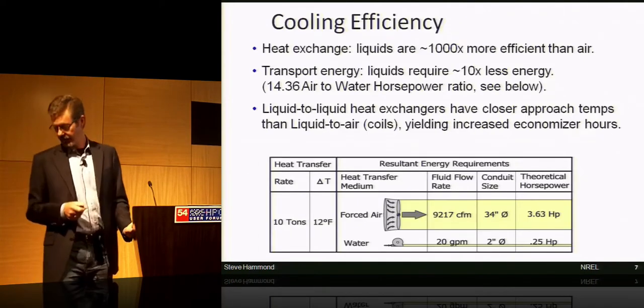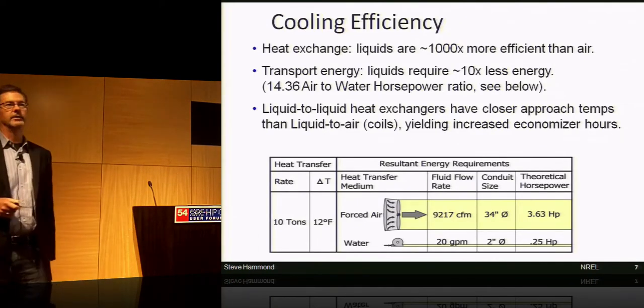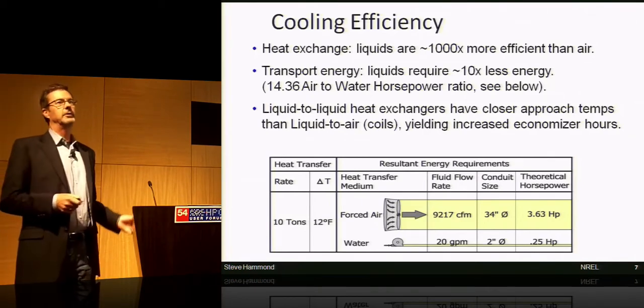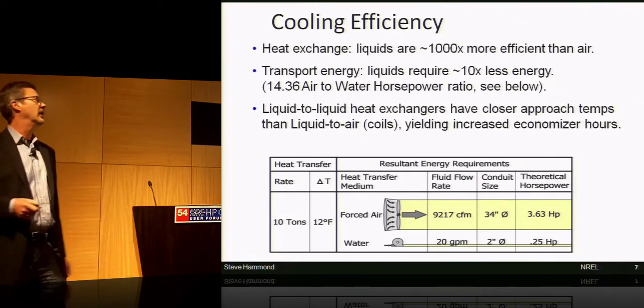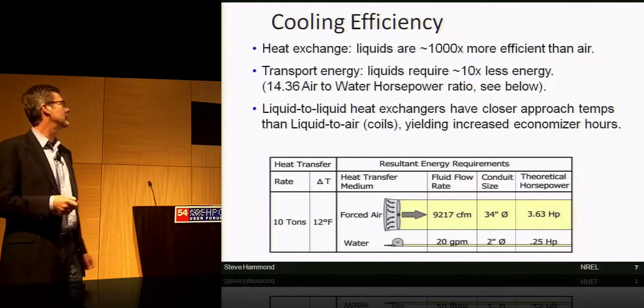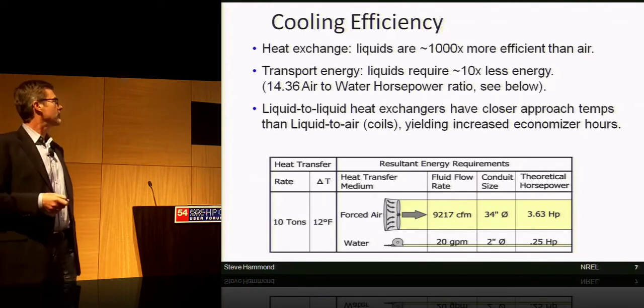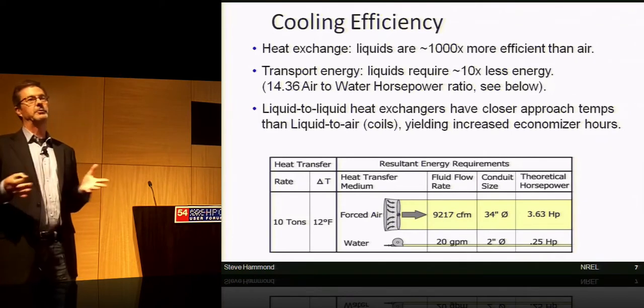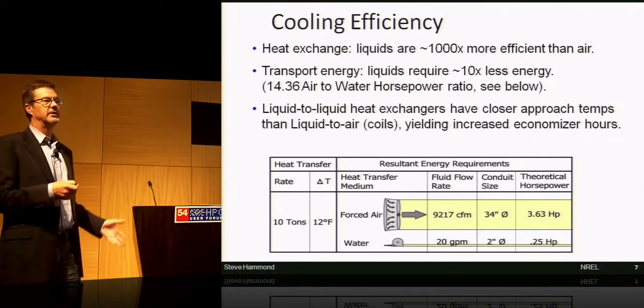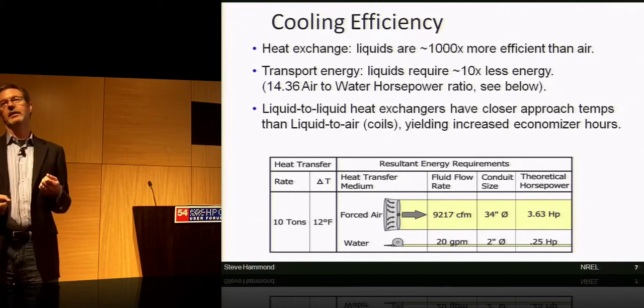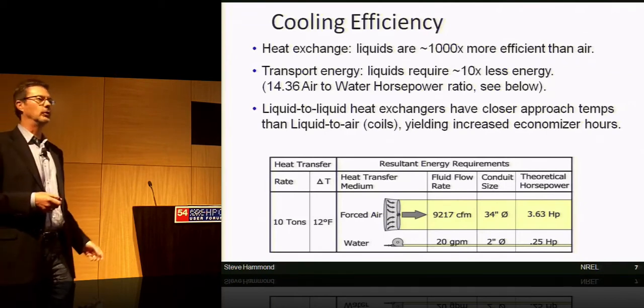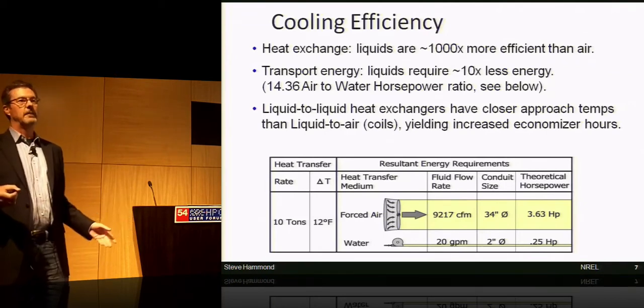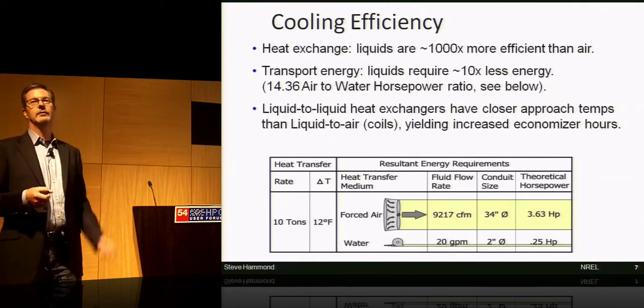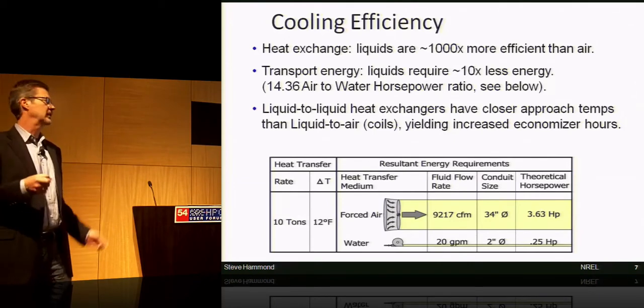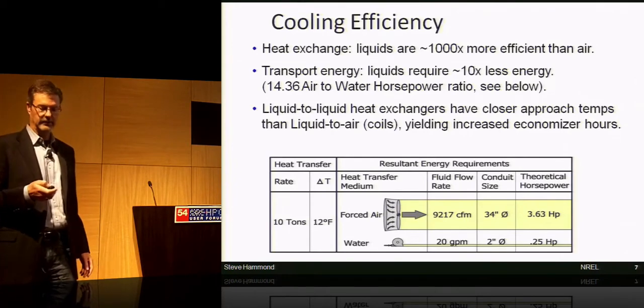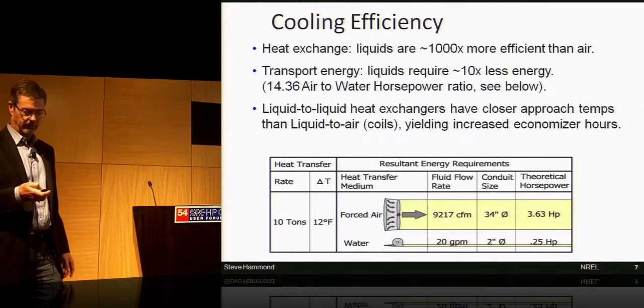As was mentioned yesterday during the disruptive technology round, liquids are three orders of magnitude more efficient than air in their cooling capacity, and transporting liquids requires much less energy from fans. I think of it as a juice glass of water having the cooling capacity of a room full of air, and the pump energy needed to move that juice glass of water is much less than the fan energy needed to move that large volume of air.